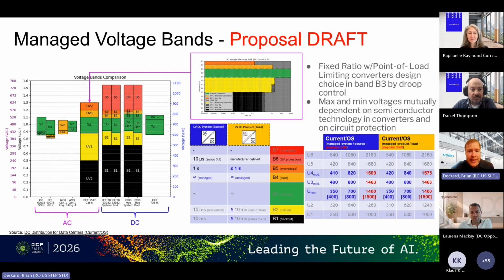Looking further at this, even though there are differences between traditional AC and DC, when you look at distributed energy resources on the AC side, they actually have a wider range of voltage support to provide than a utility would be expected to keep the power within. These wider ranges actually correspond fairly well to what is in the DC space, so you can lay out the voltage not just with regard to nominal and centering, but also with regard to time.